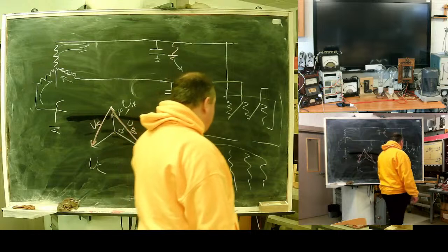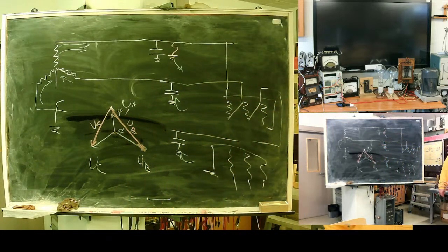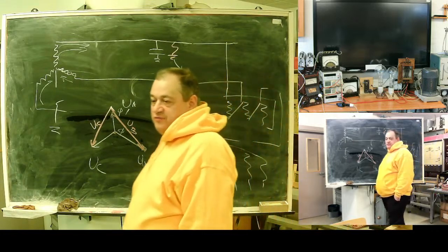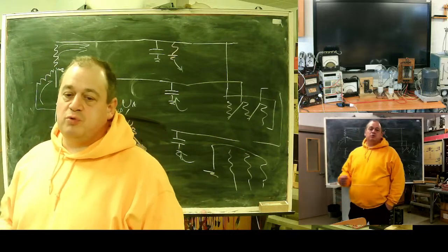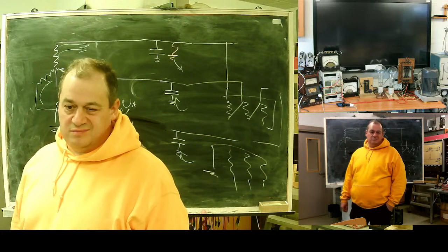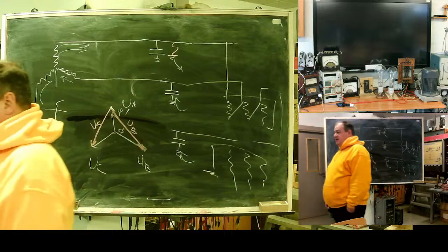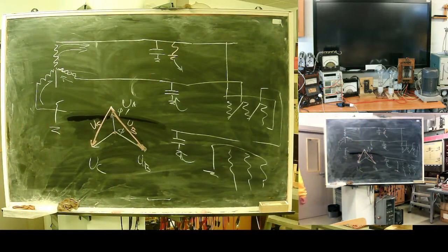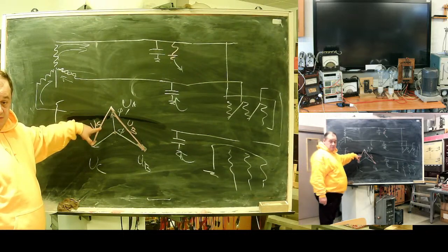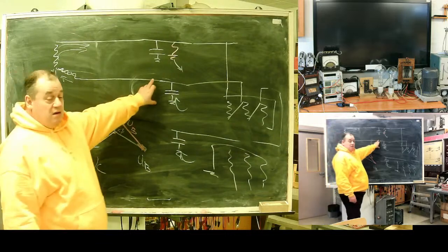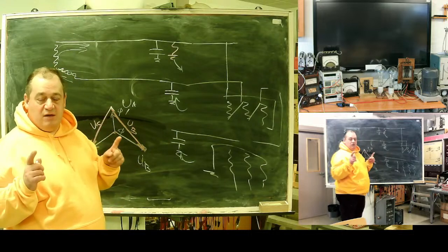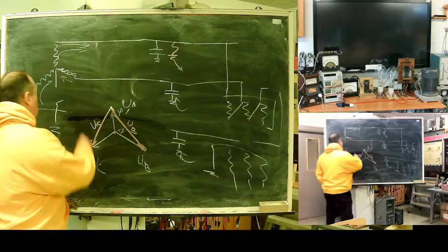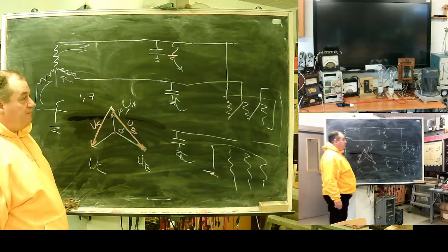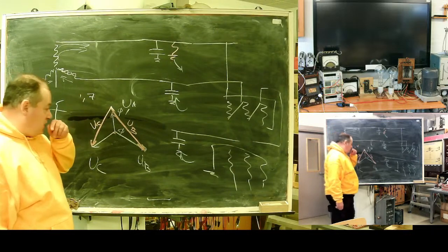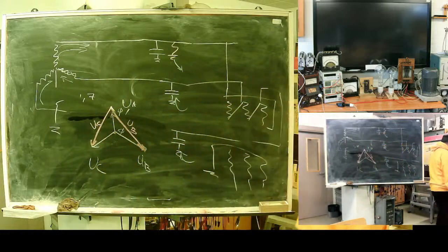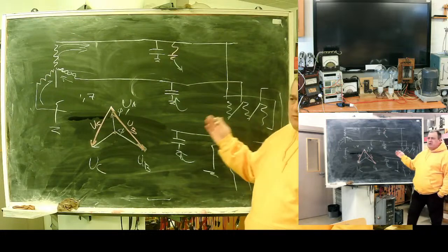Nowadays, not so easy. And why not so easy? See, a current of 10 or 15 amps does not pose a danger to the network itself at first. Let's say in our approach, actually, there are some moments when we have a voltage rise in an earth fault. Here, the line to ground voltage in its steady or enforced component will be square root of 3 times higher, and instantly in the fault moment during the transient it will be 2.6 times higher. It can cause insulation damage. But really, the network can operate.